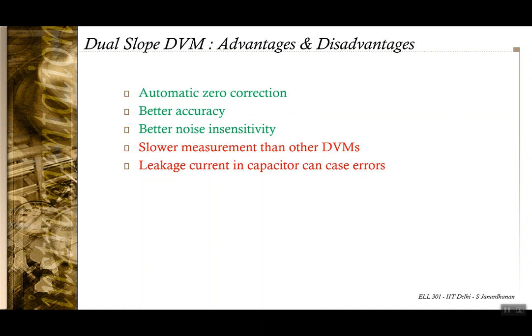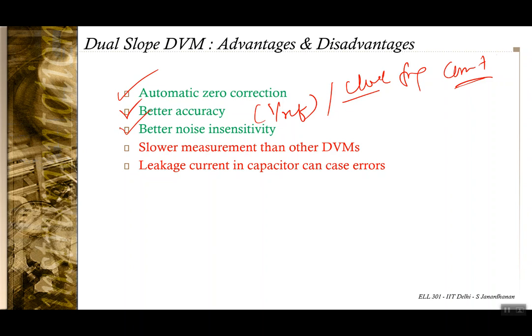For the dual slope DVM: because of the zero correction circuit there is automatic zero correction. Due to fewer assumptions — only knowing VREF and assuming constant clock frequency — it has better accuracy and is better insulated against noise. However, there are two ramp comparisons — a charging and a discharging cycle — whereas the ramp type and staircase ramp DVMs have only one ramp. So the measurement cycle is slower, perhaps measuring at half the rate of the earlier DVMs. Also, leakage current in the integrating capacitor can cause errors.